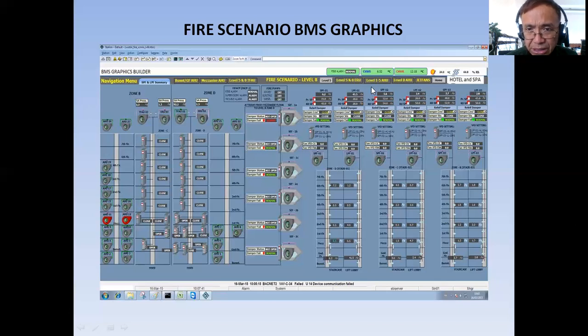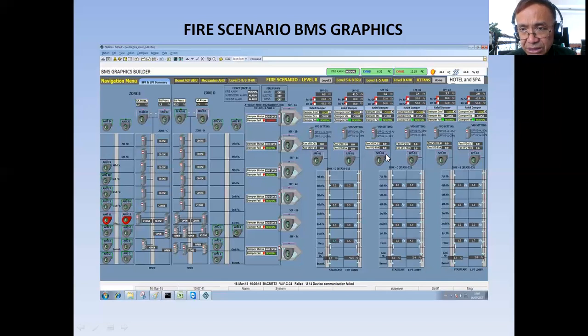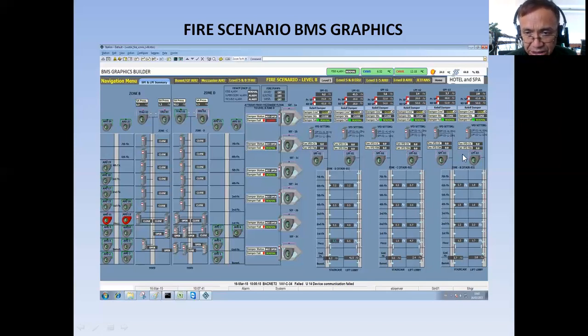I'm also giving the pressure set point. The pressure set point is around 45 Pa to be maintained in staircase pressurization one, and inside the lift lobby is around 35 Pa. You can see all the set points here, and these can be adjusted during civil defense testing, because during civil defense testing the fire officer will be checking the pressure inside the staircase and inside the lift lobby.